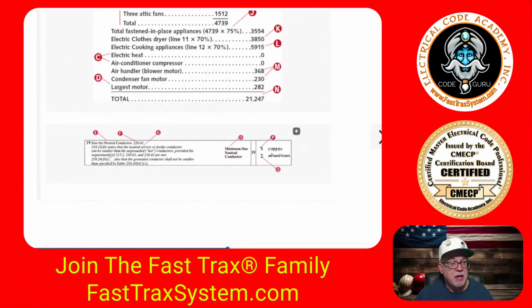And then again, this is so important. Inside of our form, so this is line 19 from the form, folks, look at the references in here. We have code references in here in order to help guide you to where you need to start this journey. Because if this service, we're doing a service, falls between 100 and 400 amps, then I have the ability to use 310.12, which people refer to as the 83% rule.